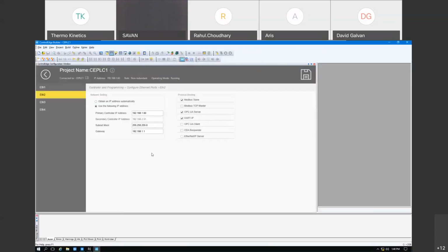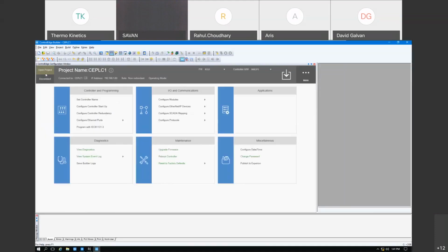So let's take a look at the configuration properties of 2. For 2, I have my IP addresses set here. For protocol binding, here's what I have to choose from: Modbus slave, Modbus TCP master. Right now I have OPC UA selected. I have HART IP, so I can manage that instrument through the PLC. I have OPC UA, CDA (controller data access), and then EIP. Okay, so that's what I have.